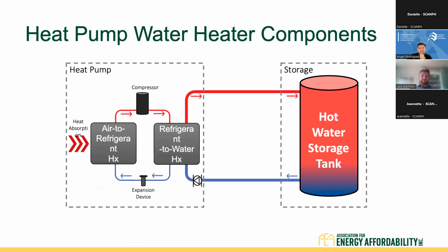Next slide, please. So opening up the hood again of a heat pump water heater, these are the components that we have. There's a lot of misconception that we have refrigerant lines and a very similar setup as we would with the split HVAC system. It's really much closer to a packaged terminal heat pump. So you have all of your heat pump components in the outdoor unit and you have water pipes in between. And then you have your standard storage tanks that are going to require the same maintenance as you had with your storage tanks for your gas water heating system.